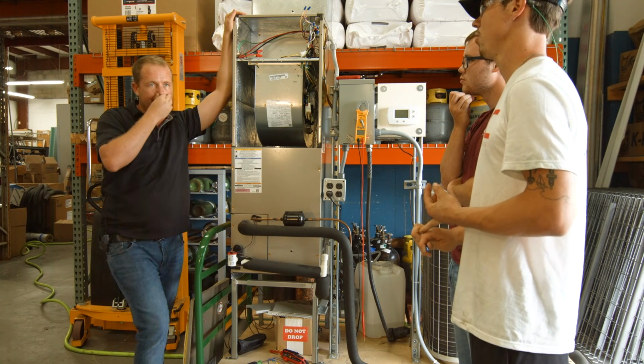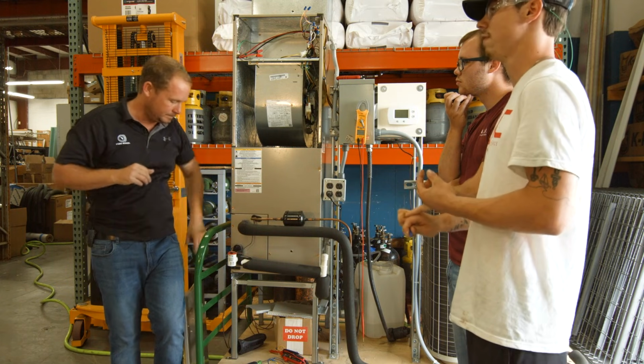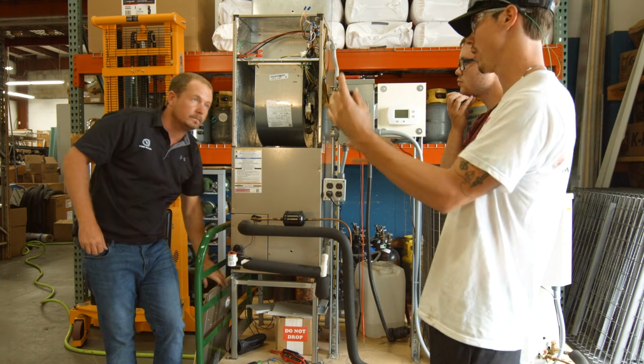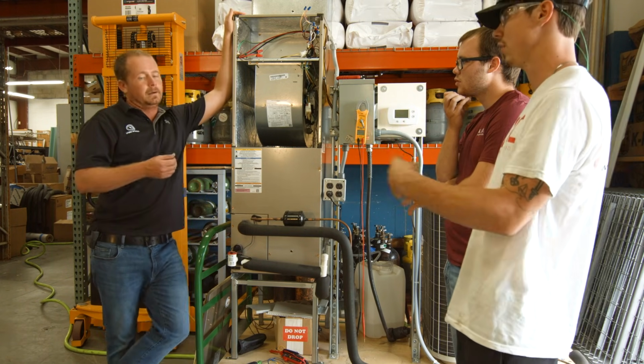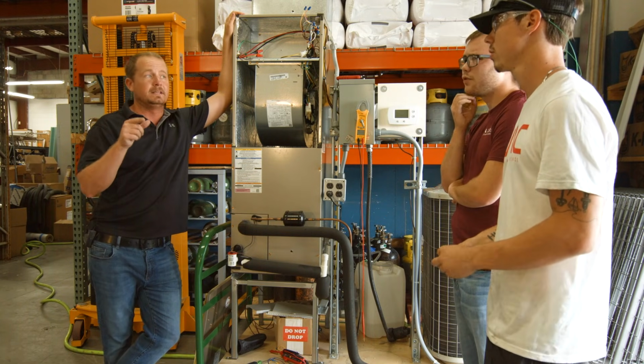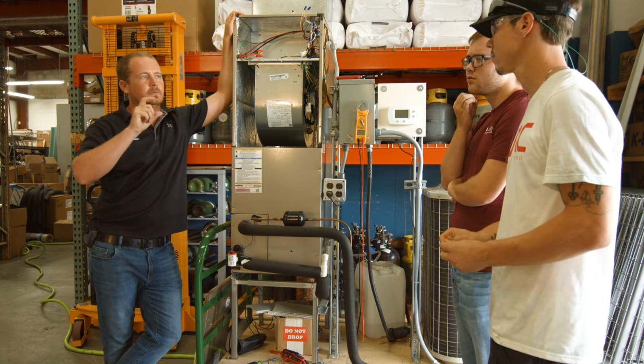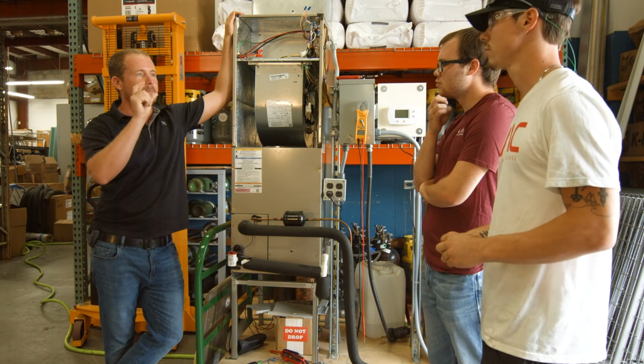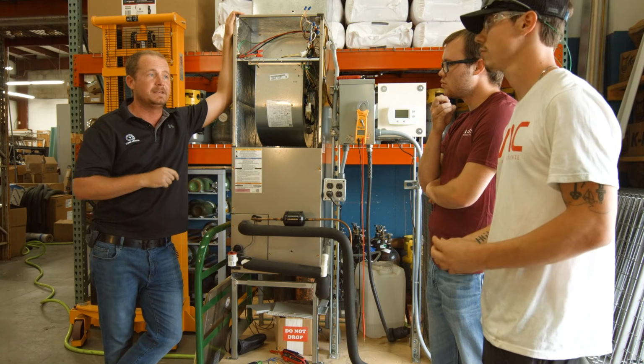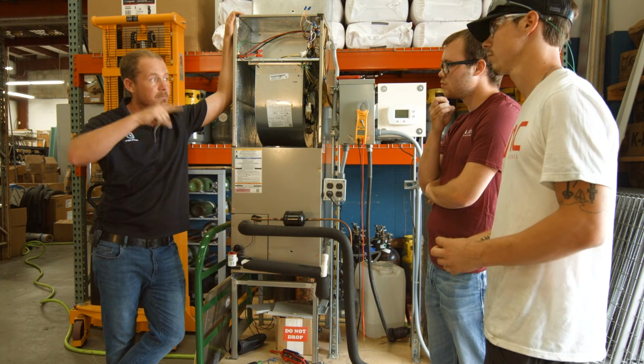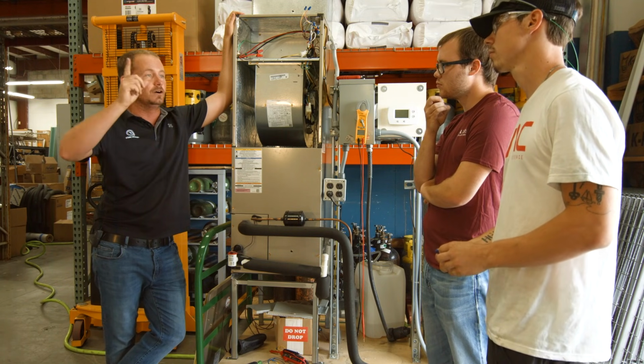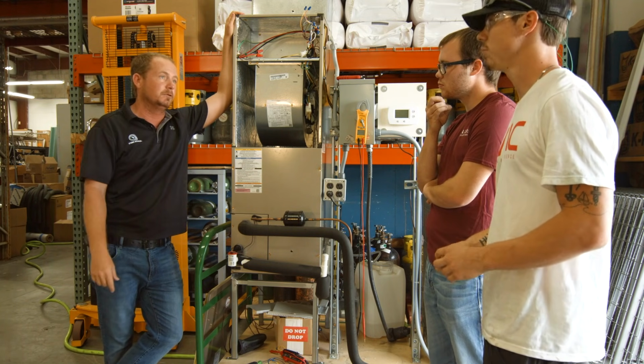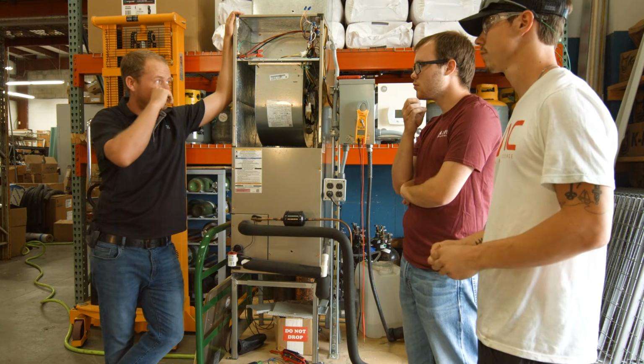Yep. And also making sure that it's set up right, because the thermostat doesn't come straight cool from the factory or set for a certain way, and changing it over. That's a big one. Another one is that a lot of thermostats had a B terminal, and they would say B blue. They would hook blue to the B terminal, but B is actually the heat mode reversing valve call. And so when it goes into heat, it would blow the fuse that way. So you'd get a bunch of those calls.